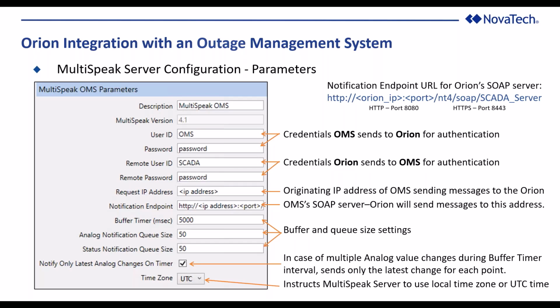This request IP address: when the OMS sends messages to the Orion, they originate from a specific IP address, and we need to populate that IP address into this field. When messages come in, it makes sure the originating IP address is what we say it's going to be. So it's critically important that this IP address is correct.